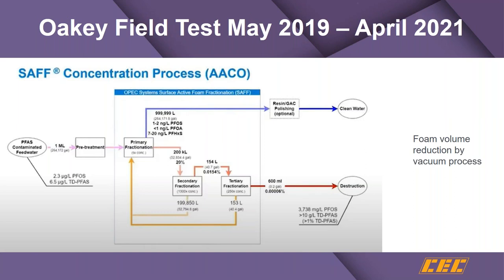In this case they have pre-filtration, then a primary foam fractionation. The residuals of the foam are passed through two different foam fractionation processes with a vacuum reduction process, resulting in significantly less than a tenth of a percent of the reject volume compared to the incoming material. They also have resin or reactivated carbon as a polishing step to produce virtually PFAS-free water.